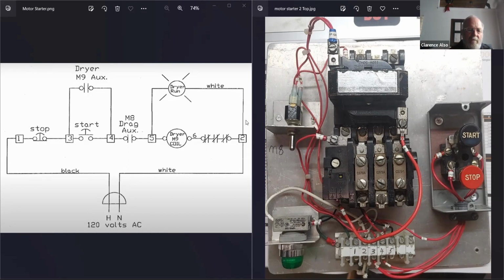But now you press the start button and it says 120 volts. Okay, so we push the start button, and now we got 120 volts at terminal number 1. Now, which direction do we go for the good 120 volts? We're at 1, so you got to go to the left of 1, and down and around.